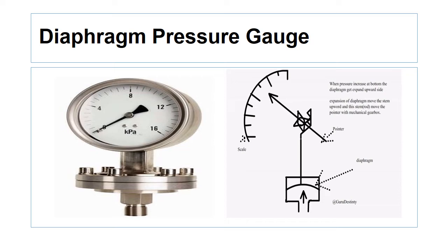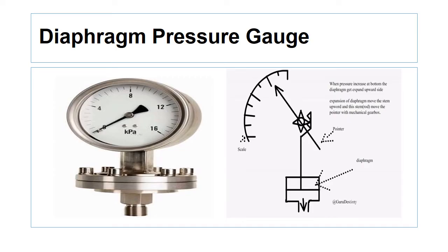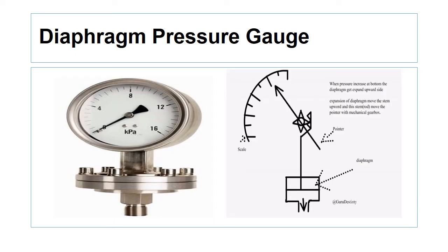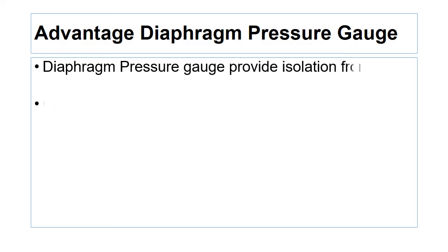The differential pressure arising across the diaphragm lifts it up and puts the pointer in motion. The deflection of the diaphragm is very small — plus or minus 1 mm. Advantages of the diaphragm pressure gauge: it provides isolation from the process and can measure low pressure accurately.